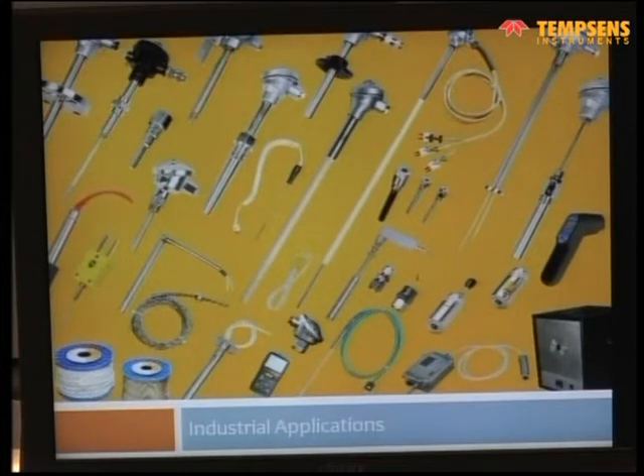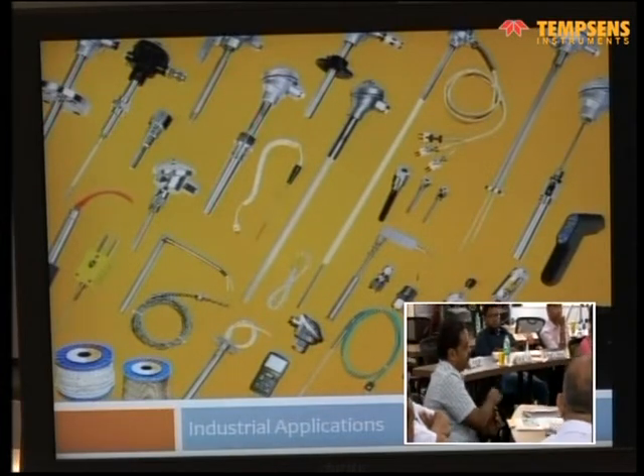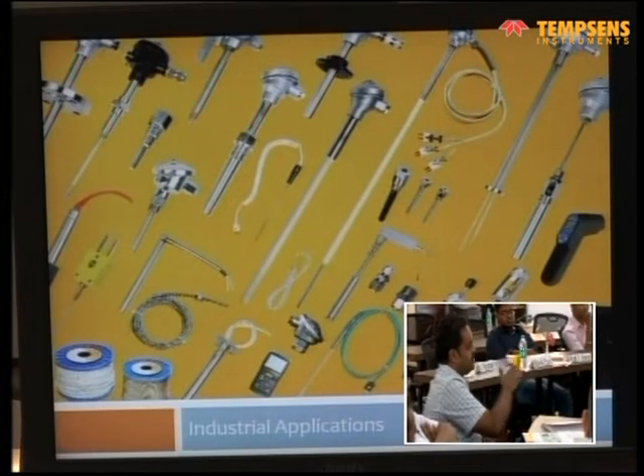Probably an example I can give: we have a conveyor brazing furnace, wherein the positioning of the thermocouple is horizontal. The application temperature is 1100 degrees centigrade, and we often find the thermowell is getting sagged down. Is it something related to the thermowell selection?